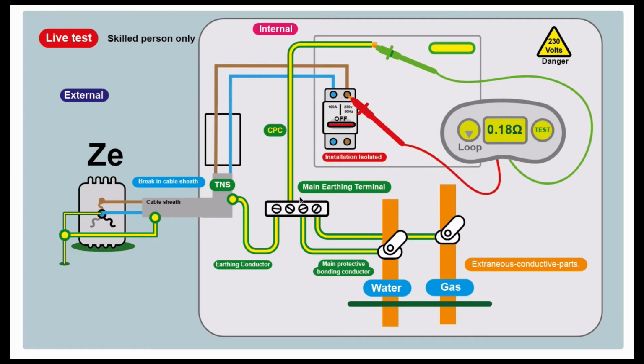So what we can do is we can either disconnect these bonding conductors, and then we could test from here. If you've got just the same one connection going all the way through, that's okay, we could do that. We'll get a reading. Even better, disconnect the earthing conductor here, then you know that there's no possibility of having any parallel paths, because you're connecting directly to the incoming source of the earth, the means of earthing. So you put your clamp on there and you probe on here on the main switch, incoming line, and then you do your test. You know you're not getting any parallel paths.